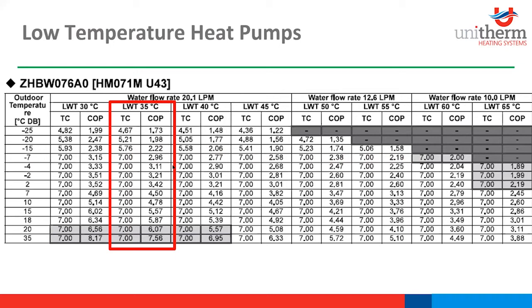But we'll just have another look here at running at even lower temperatures. If we increase the thermal mass, we can get away with even lower flow temperatures, lower leaving water temperatures. So we'd say design conditions here in Uni-Therm, you're designing at -3. So basically worst case scenario, on average, the weather in Ireland is generally 10 degrees on average. That's what they say. So at a 10-degree average weather, it's 7 kilowatts, you're getting a COP of 5.14. So for every 1 unit of electricity you put in, you're getting 5.14 out.